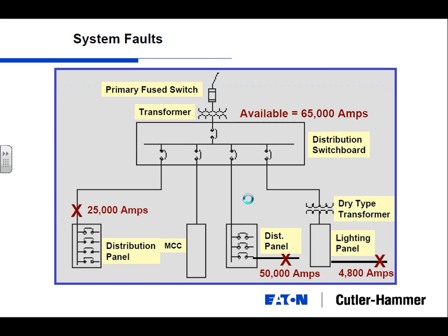So looking at how it would normally look, coming out of that transformer, I may have 65,000 amps available here, 25,000 amps fault current available at a distribution panel, 50,000 amps in this distribution panel, and only 4,800 amps in this lighting panel. Pretty big spread. If I'm looking at this at one glance, I see this is 65 and this is 50. This distribution panel is probably going to be near this switchboard. This distribution panel at 25, there's two things that are going to lead to it being a lower fault current.